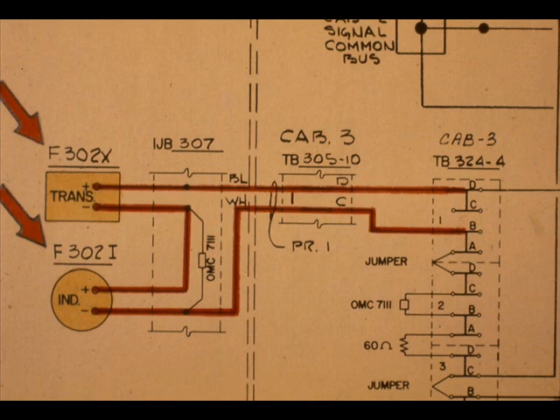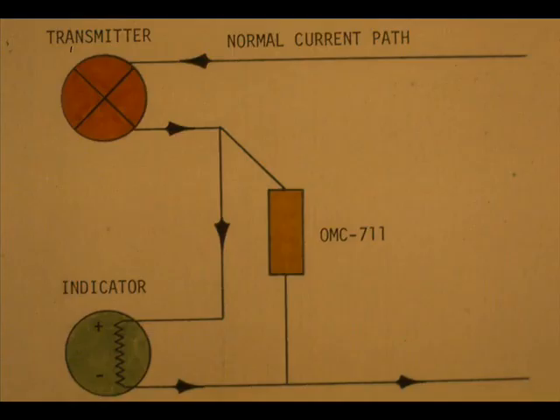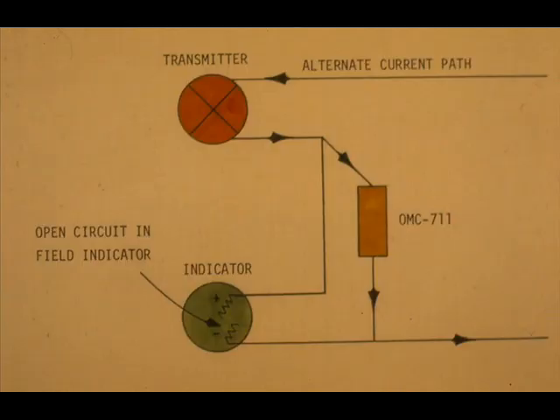Take a close look at the current paths through transmitter F302-X and field indicator F302-I. There are two paths for current. The current normally goes through the indicator. But suppose the field indicator malfunctioned and sustained an open circuit.